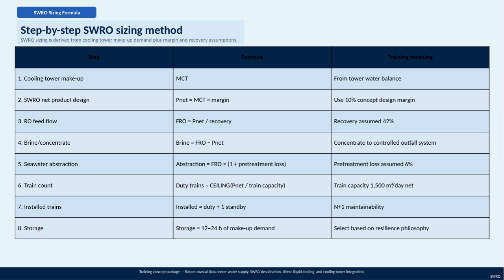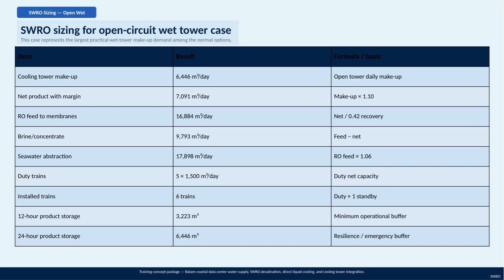Batam Coastal Data Center. Here, we're looking at the sizing for the seawater reverse osmosis system in an open wet cooling tower scenario. This setup represents the largest practical makeup water demand typically seen with wet towers. Starting with the cooling tower, it requires about 6,446 cubic meters per day to make up for water losses. To ensure a safety margin, we increase this volume by 10%, giving us a net product water supply of just over 7,000 cubic meters daily.